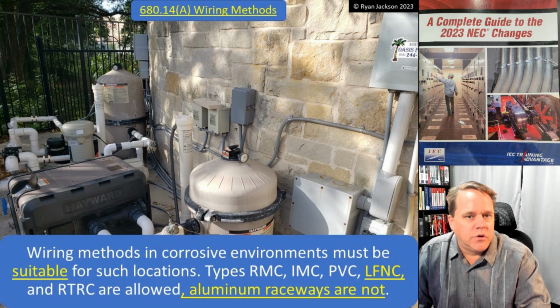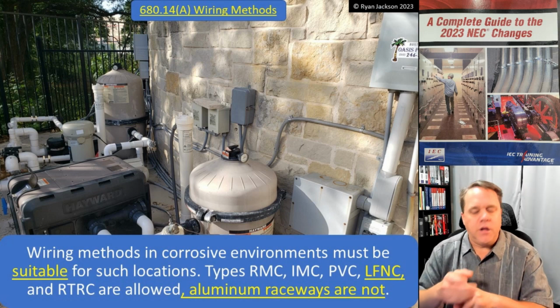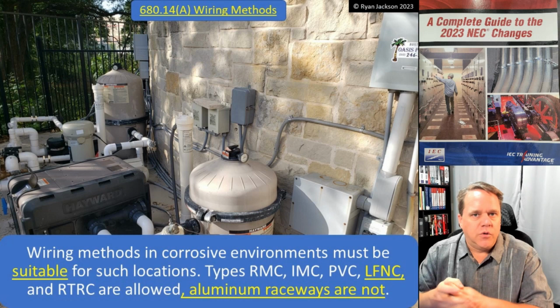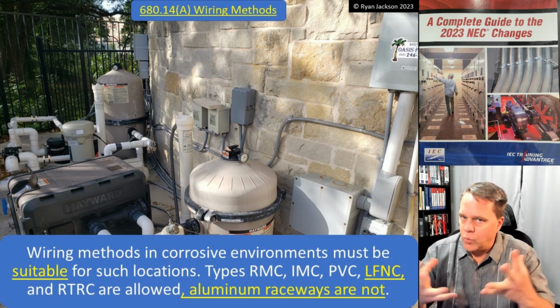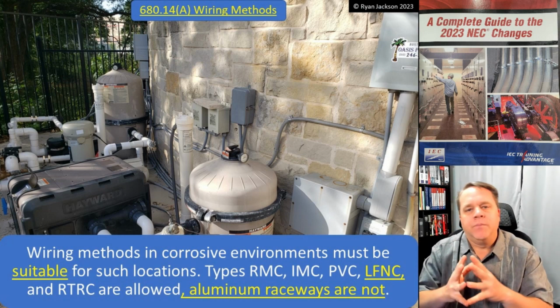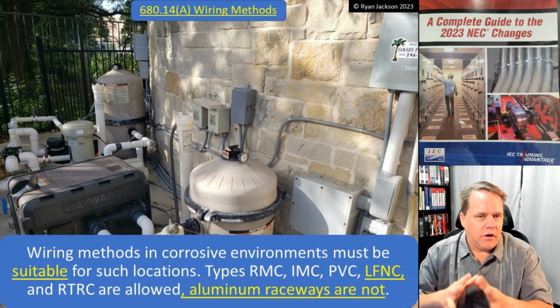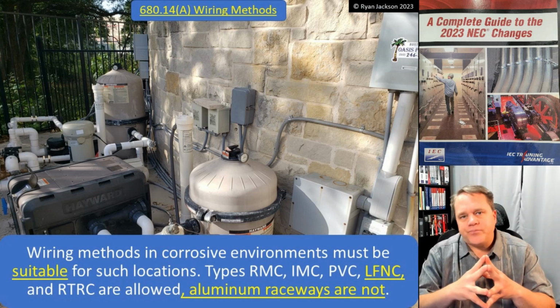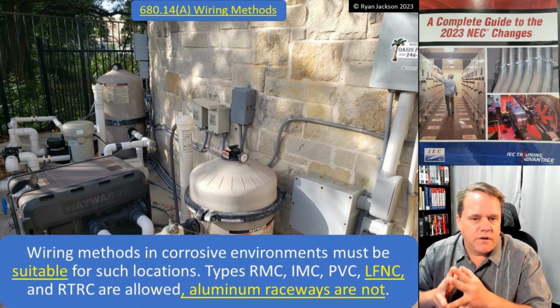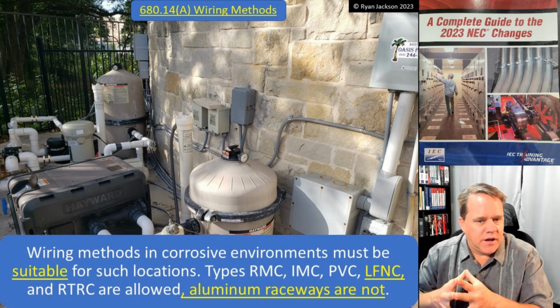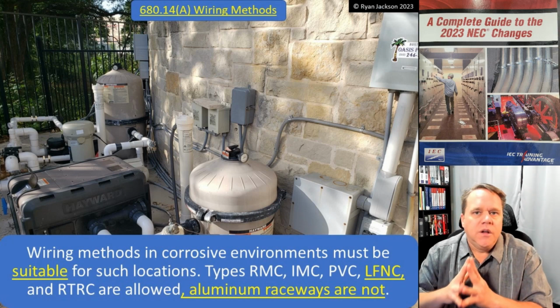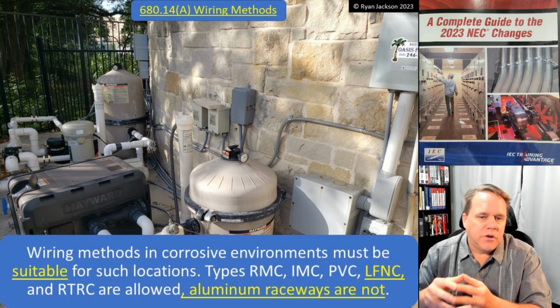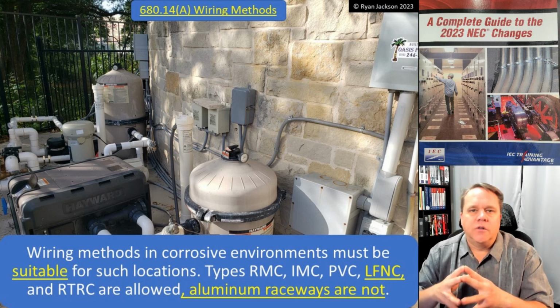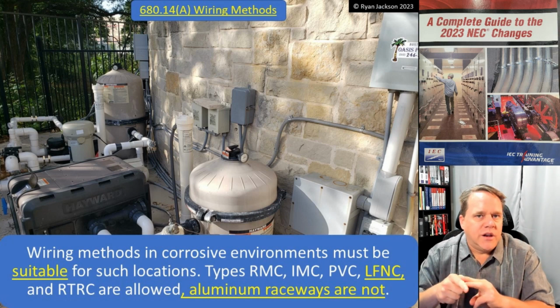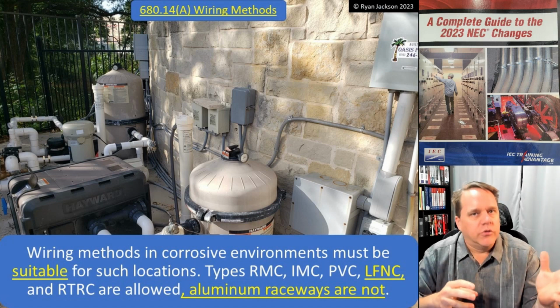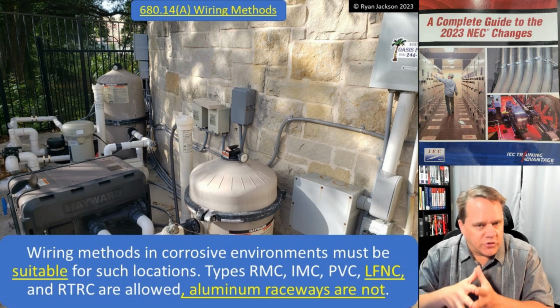680.14(A) talks about the wiring methods. That's going to be your EMT, your PVC conduit, rigid metal conduit, liquid type, whatever the wiring method is. And then subsection (B) is going to talk about the actual equipment itself. So 680.14(A), wiring methods in corrosive environments must be suitable for such locations. Rigid metal conduit, intermediate metal conduit, PVC conduit, liquid type flexible nonmetallic conduit, and reinforced thermosetting resin conduit, that's fiberglass. Those are all allowed. However, aluminum raceways are not.